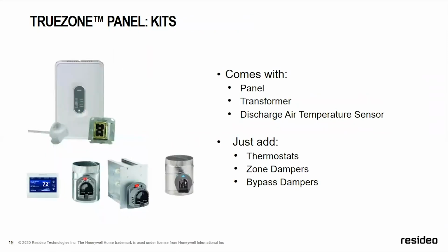Zone panel kits. This is what comes with a zone panel kit. You get the panel, you get the proper 40 VA transformer, and you get a discharge air temperature sensor. Highly recommended. You should always be buying a kit. Just add the thermostats, the zone dampers, and the bypass damper. More on that later.